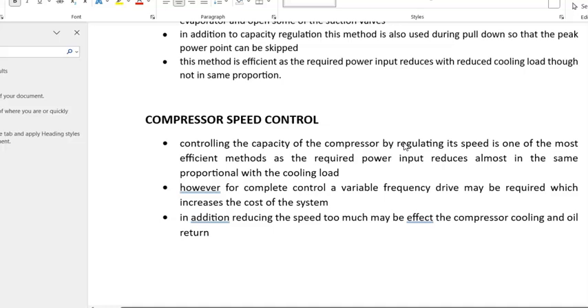Compressor speed control. Controlling the capacity of the compressor by regulating its speed is one of the most efficient methods, as the required power input reduces almost in the same proportion as the cooling load. So it is more efficient because in the same proportion as the cooling load, the power input also reduces.